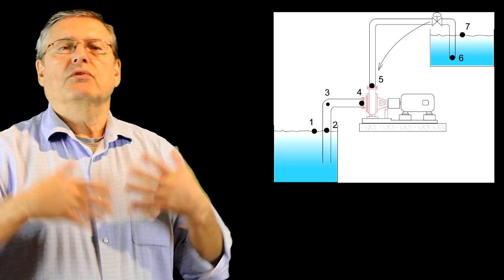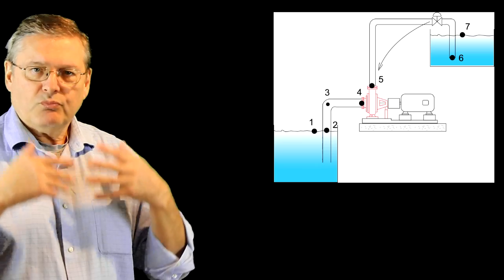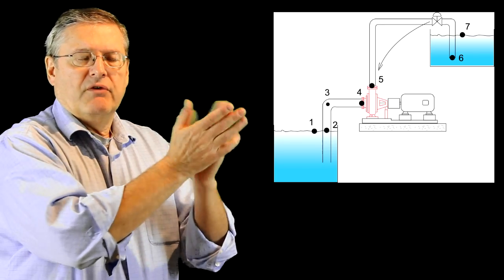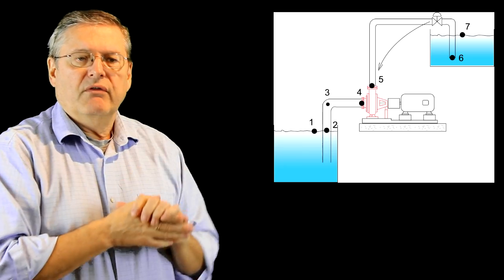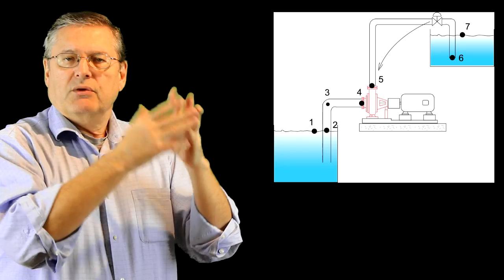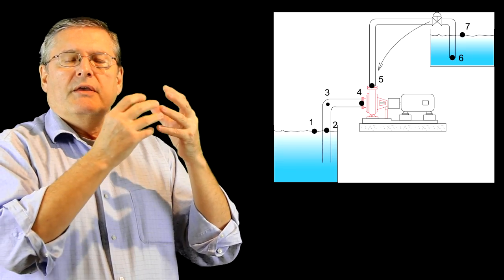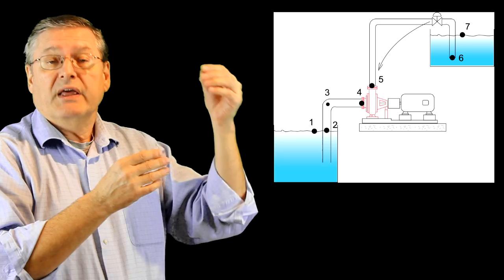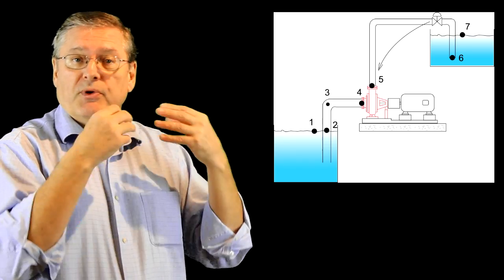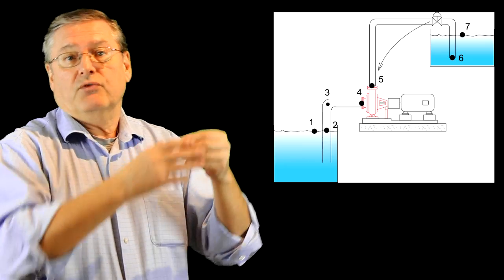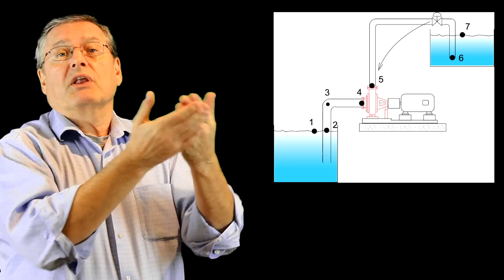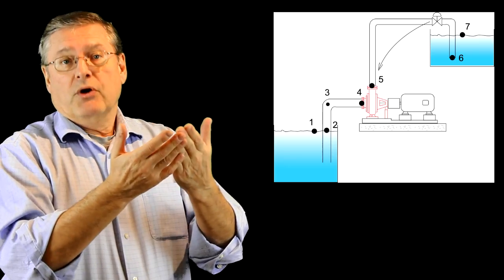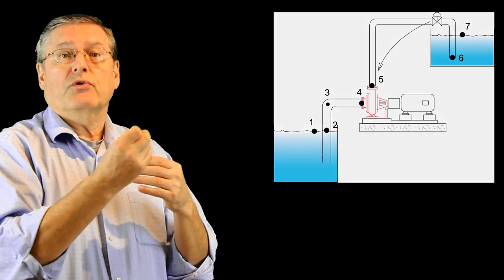So what happens if we put a control valve right before the tank? Control valves are less commonly used now because of variable frequency drives, but they're still found in older systems. If we put the valve there, the chances of cavitation or improper function due to low pressure are high, because we'll have low pressure at that point. A valve operates best when there's sufficient pressure at its inlet. A better location for a control valve is closer to the pump discharge, where there's ample pressure.